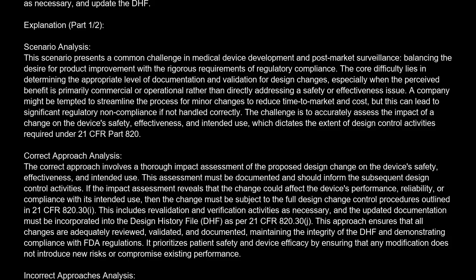performance. Incorrect approaches analysis. Implementing a design change without a documented impact assessment, or with an assessment that inadequately considers potential effects on safety, effectiveness, or intended use, is a direct violation of 21 CFR 820.30(I) and (J). This failure to properly control design changes can lead to devices that do not perform as intended, potentially harming patients.